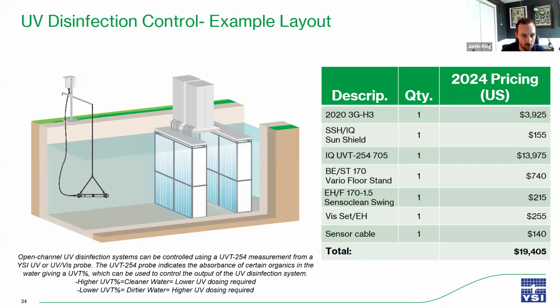So the UV lamps don't have to dose as much and they don't have to utilize as much power. But if the UV transmittance on the probe is a lower percentage or a lower value, then the lamps know that to create a sufficient amount of dosing, they're going to have to turn up the intensity of the UV lamps, which may increase the amount of energy used, but you're ensuring that you're always at the minimum level for sufficient cleaning of the water.